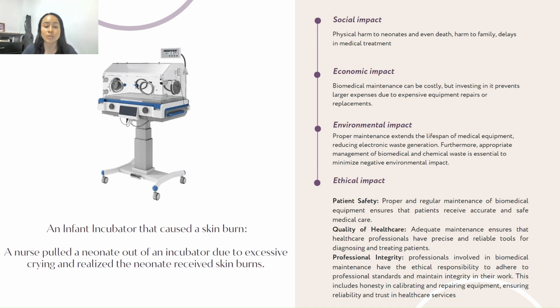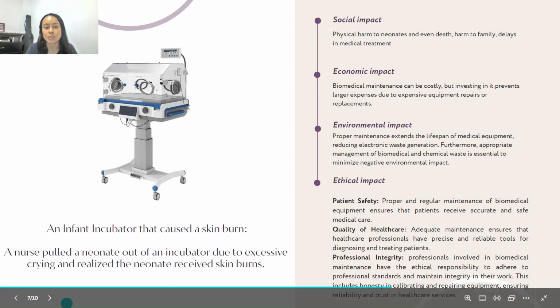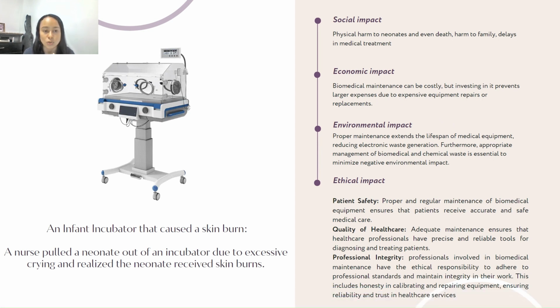We find that in Colombia, several cases have been reported where babies have died or suffered burns due to the malfunctioning of the incubator. The impacts of our actions in a social way can directly influence the health of the patients and their family, delaying improvements in the state of health. We want to ensure the medical device works every time and without failure. On the economic side, the maintenance is done in order to extend the life of the equipment, which means less cost in repair and spare parts. And another point may be that it will avoid lawsuits to the hospital due to equipment failures. This is really important to have in mind.